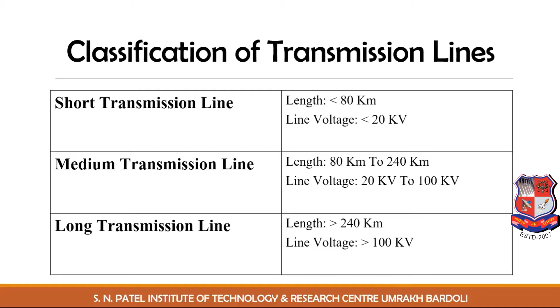Medium transmission line. In medium transmission line, length is between 80 km to 240 km and line voltage is between 20 kV to 100 kV. Due to appreciable length and voltage of the line, capacitance effect is considered in medium transmission line. In long transmission line, lines having length above 240 km and line voltage above 100 kV are generally considered as long transmission line.